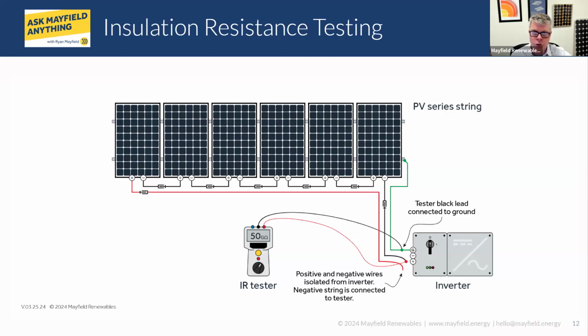And here we're showing a single string of modules coming to an inverter. So isolating the positive and the negative, what we're able to do there is connect the tester to the negative leads of our home run conductors, and we're essentially pressurizing that entire array. We're putting voltage across all of those modules, across that red positive home run wiring coming back. We are pressurizing that line and trying to see if we have any leaks to ground.